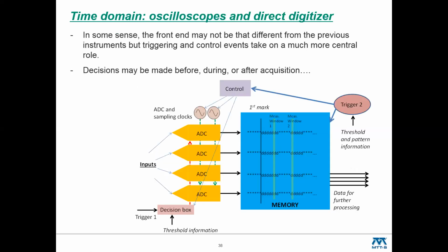And shifting gears now into time domain, if you notice, the structure doesn't look a whole lot different from the earlier pictures, aside from a little more detail. But of course, in practice, there is a fair amount going on, particularly in the realm of triggering. Now, all the analyzers before have some kind of acquisition triggering kind of scheme that's required, but there's obviously typically a lot more choices in a time domain tool, since you're looking for transient information, generally speaking. And importantly, there are two varieties of that kind of triggering.